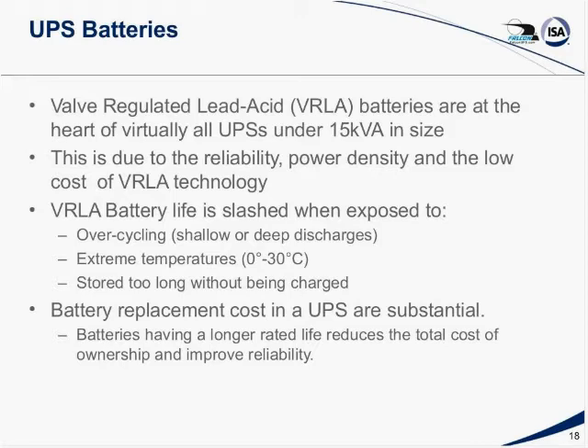In the case of the line interactive and offline UPS, every time the utility line or the AC line goes out of regulation, the UPS has to go to battery. So with an offline and a line interactive, you end up with a lot of cycling on the battery. In a typical VRLA battery, the cycle life may be 1,000 to 3,000 cycles. With an online UPS, the battery is mainly used in float mode, and you don't have a cycling problem. But you do have, with all the UPSs, extreme temperatures. High temperature is the great destroyer of batteries.